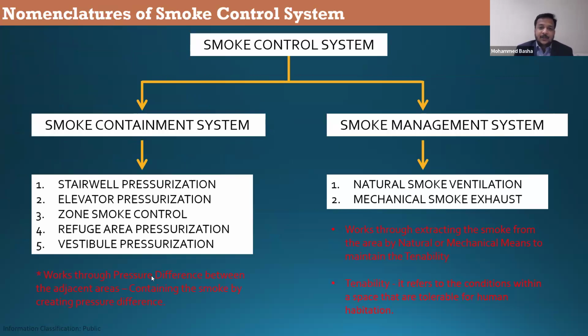So let's look into the smoke control system basics first, because we often hear the term smoke control system. But what exactly is a smoke control system? How many systems are there? Smoke control systems are divided into two types, as you can see here: smoke containment system and smoke management system. The smoke containment system works through the pressure difference between the barriers. It means you are containing the smoke in one place by creating a pressure difference between one space and another space. The examples are stairway pressurization, elevator pressurization, zone smoke control, refuge area pressurization, and vestibule pressurization.